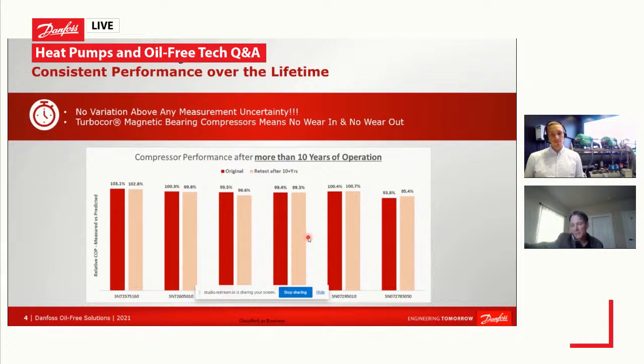Since Turbocor has been around for 25 years now, we have a good sample of existing units out there in the market, primarily on chiller applications. But what we did, or what we can do, is buy back 10-year-old compressors to retest them in the factory. So we test them before they go out the door, when they're produced, and then 10 years later when we buy them back. And then compare that performance to see how the compressor itself is performing in comparison to how it was when it was first produced. And what you see is a summary of that here.